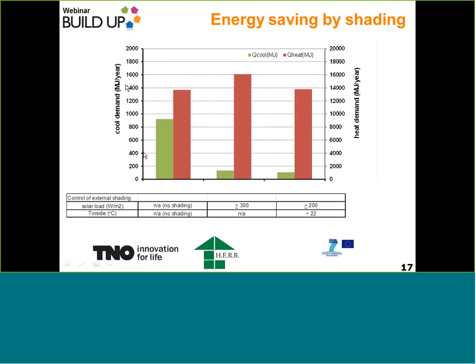To show that, here are the same strategies. What you see here is the cooling load, the green one, and in red is the heating demand, on different scales, about 10 times more. This is a typical situation in the Netherlands with no shading applied - you see a cooling load and a heating load. When shading is applied only with a light sensor, you see an increase in heating demand and a decrease in cooling demand, but the total is more than the first situation. By also controlling on indoor air temperature, you see a reduction in cooling demand, while heating demand stays the same.